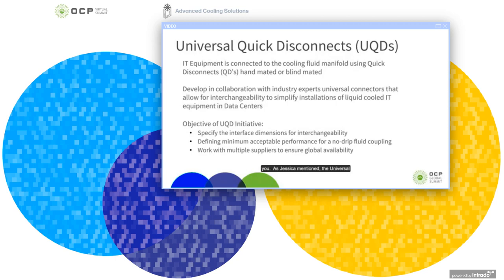As Jessica mentioned, the universal quick disconnect, or the quick disconnect, is a critical function of the fluid cooling loop. The connection between the cabinet manifold and the IT equipment is where that connector lies. And that connector can be disconnected while the fluid loop is running, and it will stop flow in both directions. That allows the suppliers or the data center owners to replace equipment without shutting down the entire loop. So it is a very critical part within the fluid loop.